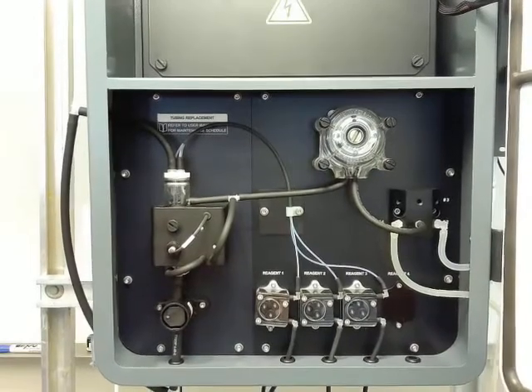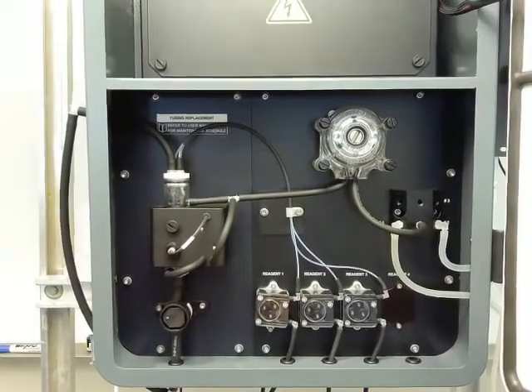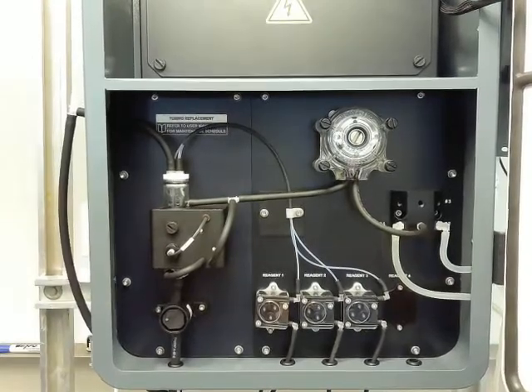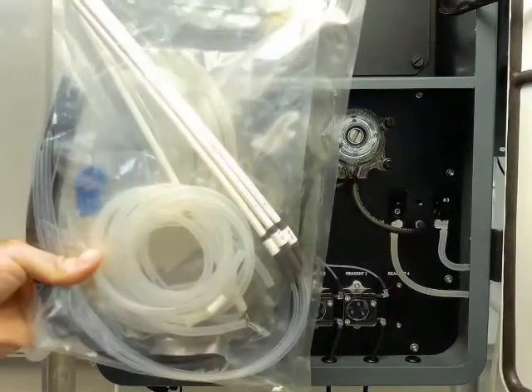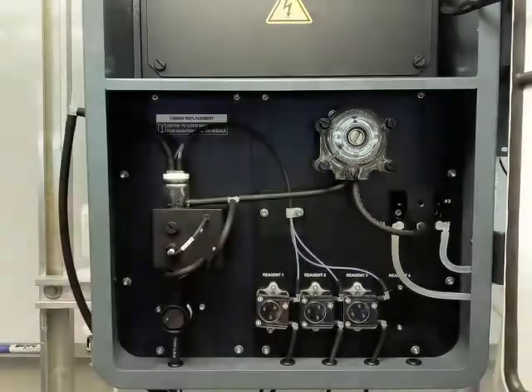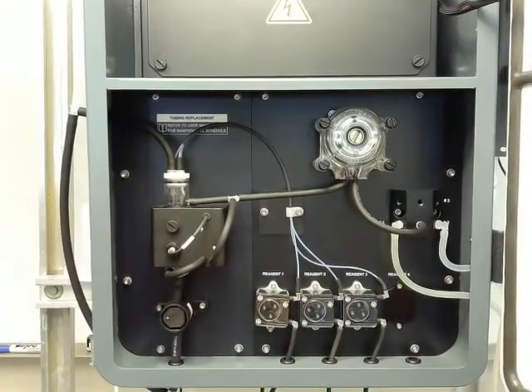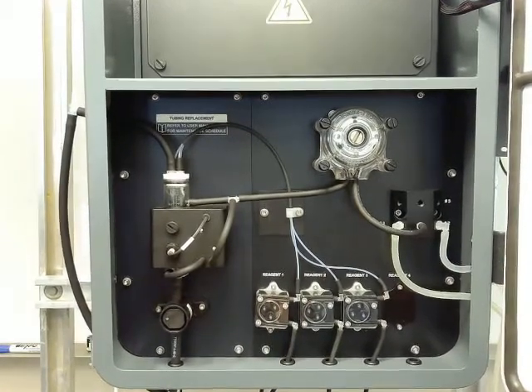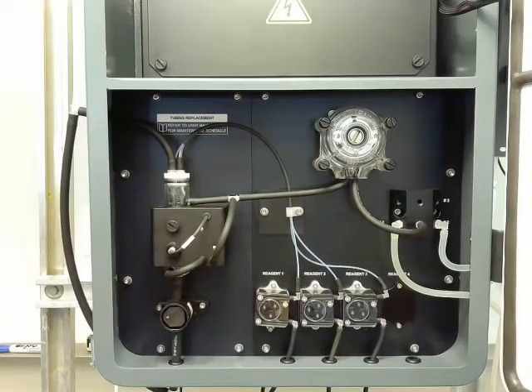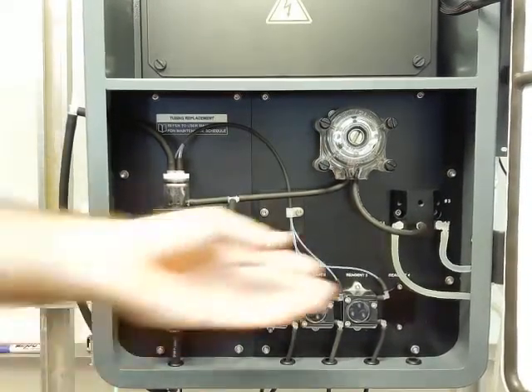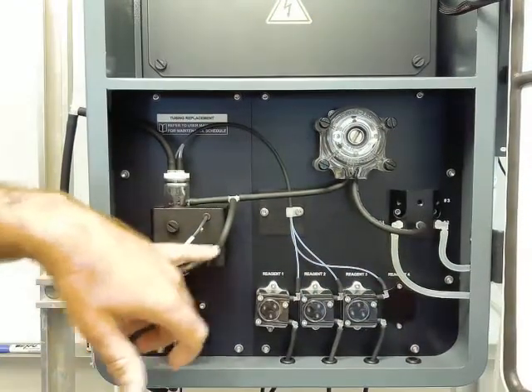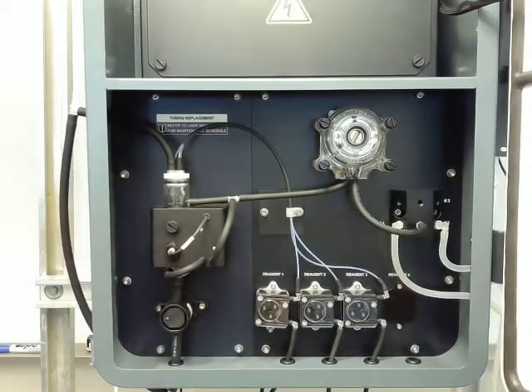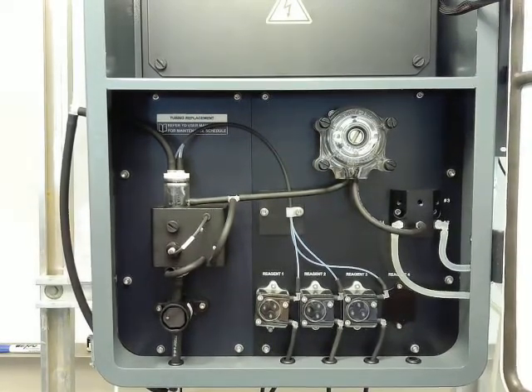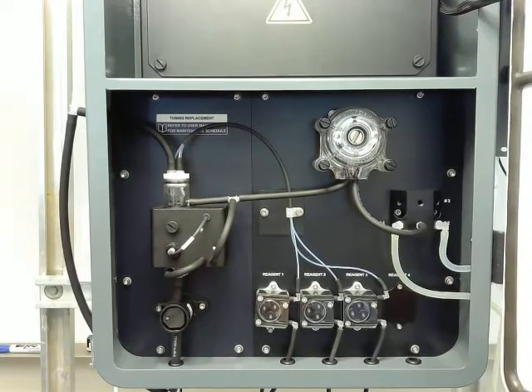So with these tubings, we kind of recommend quarterly replacement, based on running all the time. Supplied with the analyzer, or as an extra, is this tubing kit, which basically comes with all the tubing that you need for a full year's replacement. So it'll come with 4 drain tubings, 4 sample pump tubings, enough reagent pump tubings to do all the reagent pumps 4 times a year. And then also the extra tubings like the sample lines and these mixing tubings that don't have to be replaced as frequently because they're not under any compression and being worn. It's more just cosmetic, if they start to get dirty, replacing them for looks.